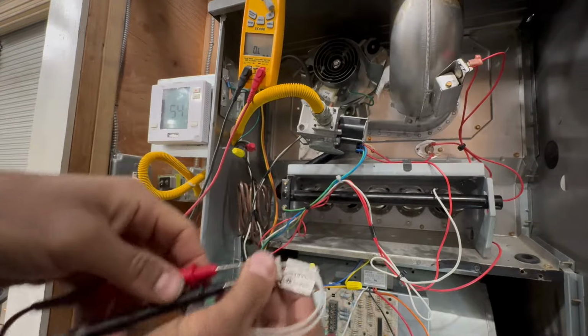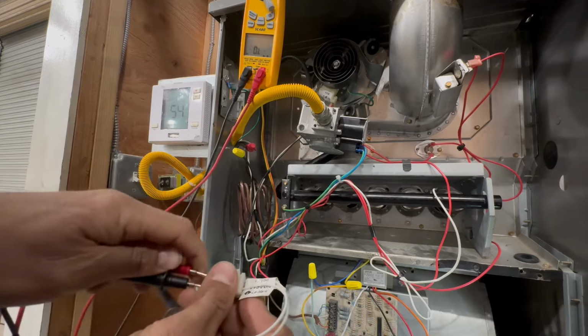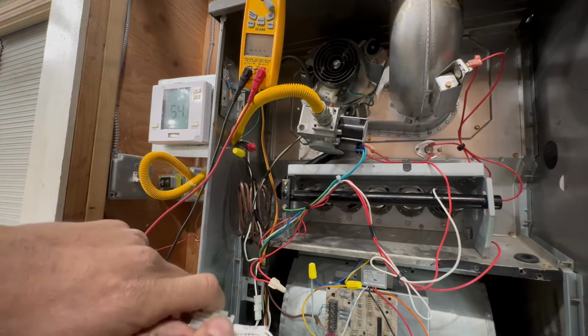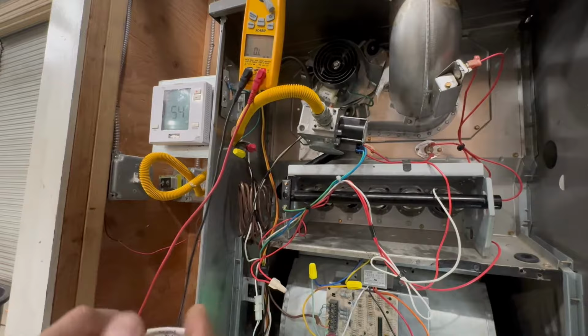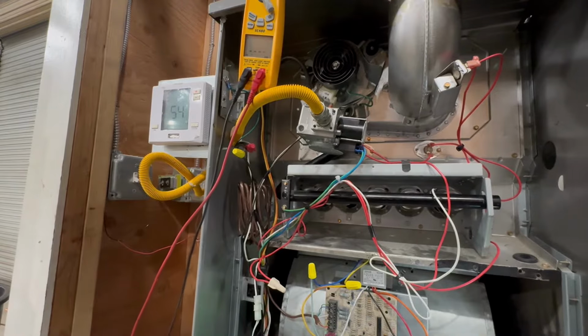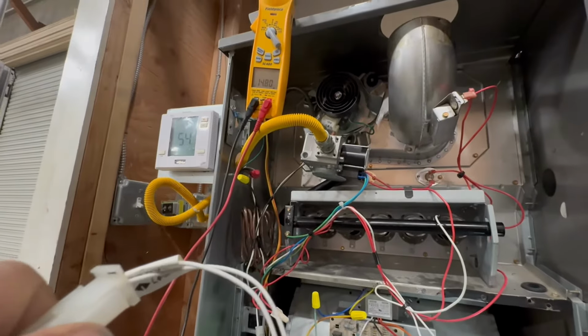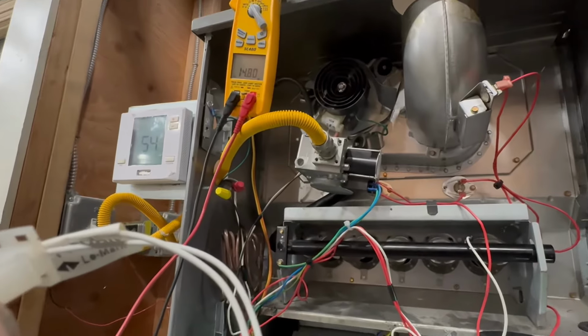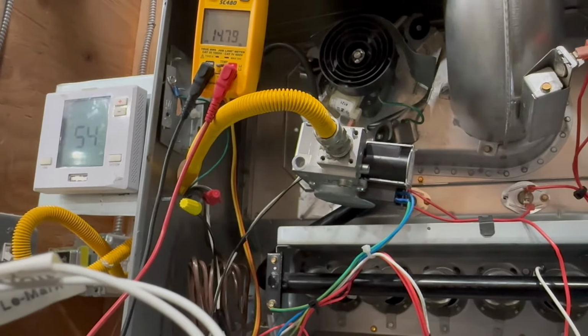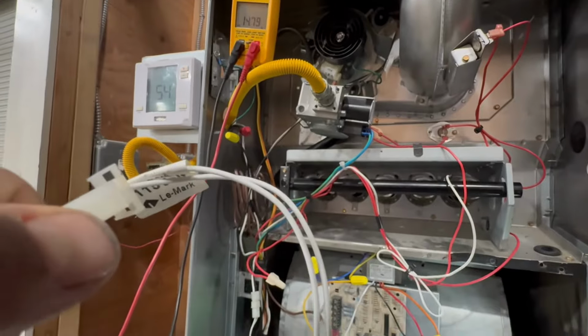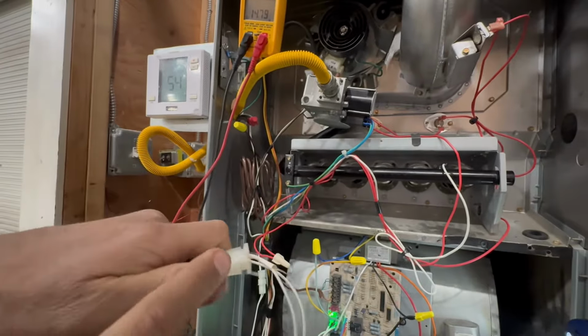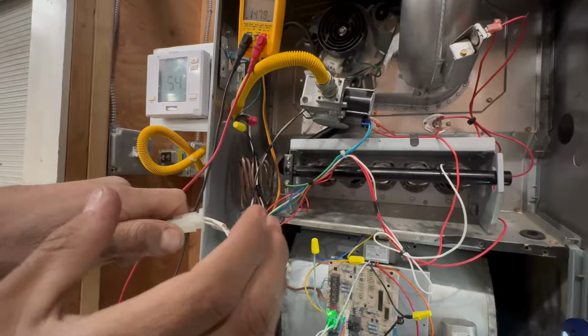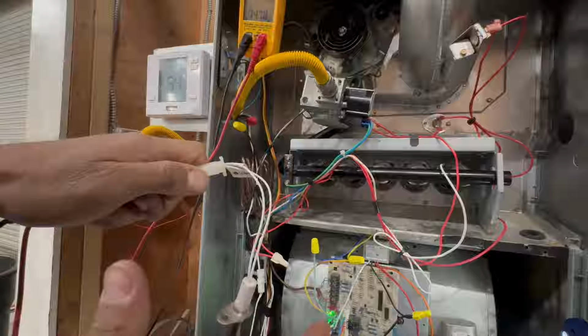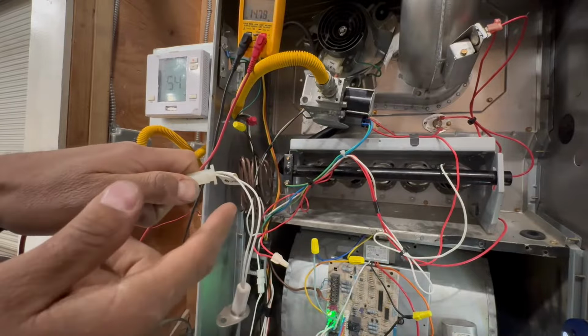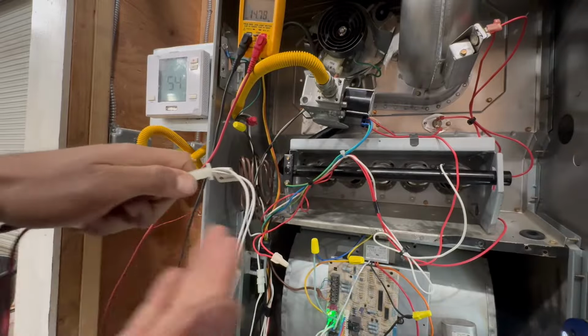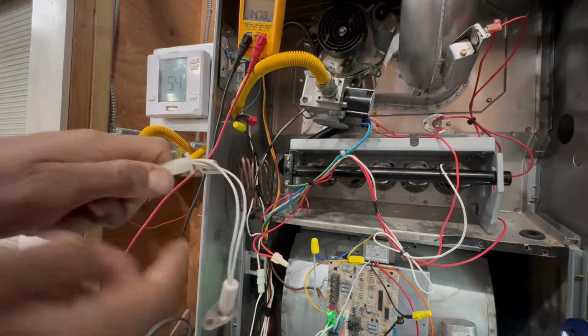So basically what it is, and I'll show you right now. First, let's get a reading. So look at the meter right there. I'll do a closer look up. I'm reading 14.8 ohms, 14.8. So that's good. That's a good reading. And actually, different hot surface igniters will have different resistance values that you're looking at. So you can simply go to the one you're buying, look up the document, and it'll tell you what you're looking for. But you do not want to see open line.